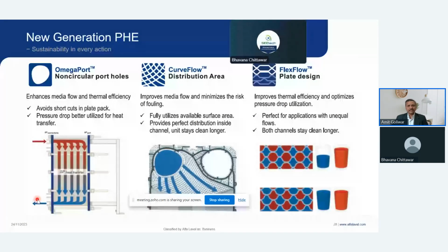Having said that, the plate heat exchangers which are currently available have also gone through a lot of innovation, and it is not necessary that all the PHE ports should be circular in nature. You can have ports which are omega shape or oval shape, because when fluid flows from a pipe, if you see, the center of gravity moves and it makes an oval shape. So by just making the ports oval shaped, you can reduce the pressure drop by approximately 20%. And a 20% pressure drop reduction is like a 20% saving in electricity.